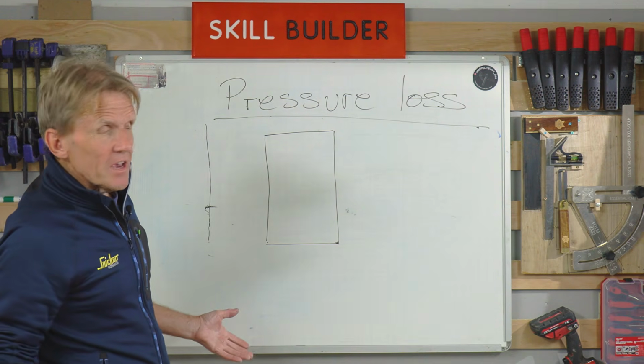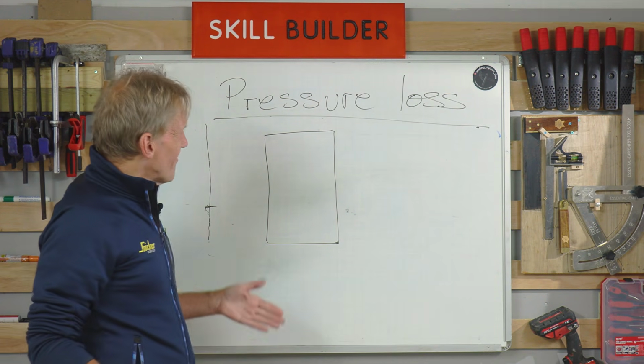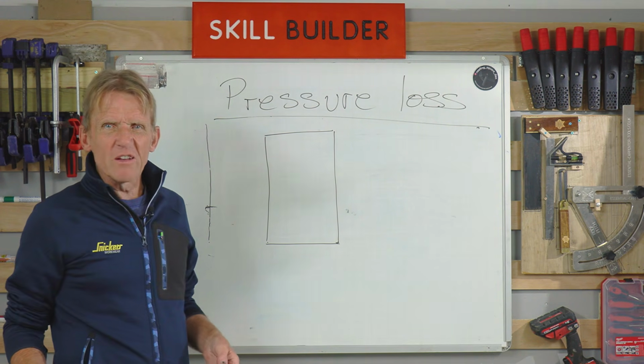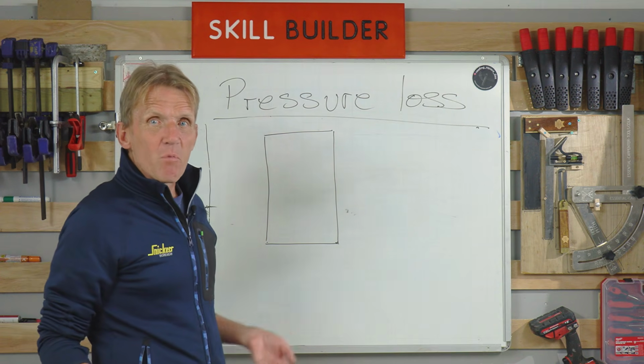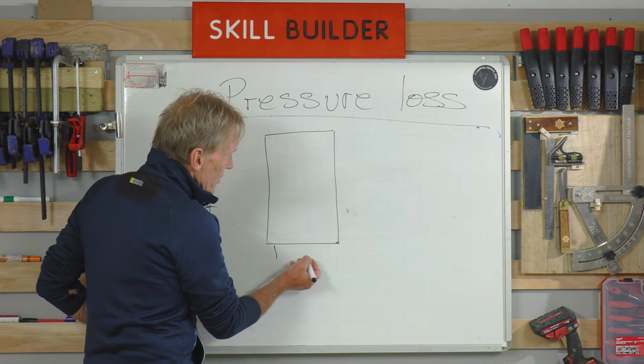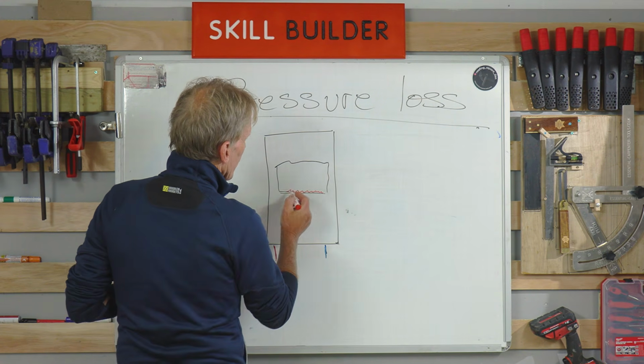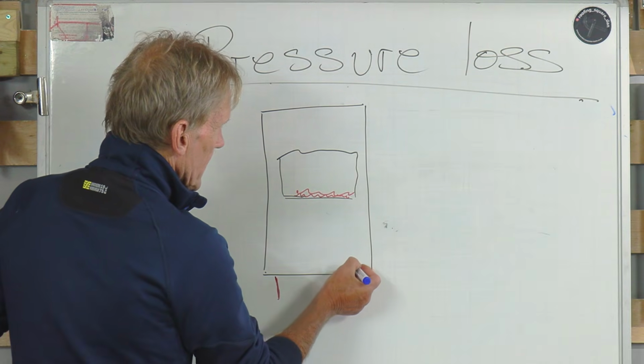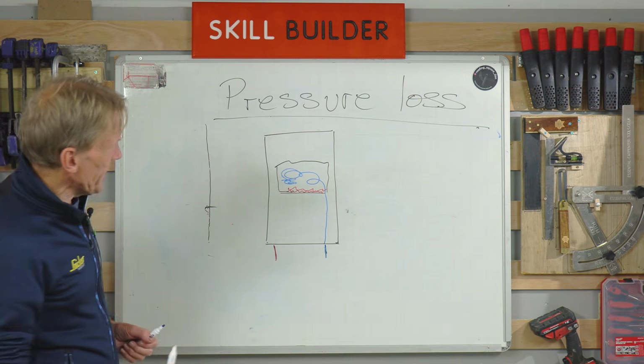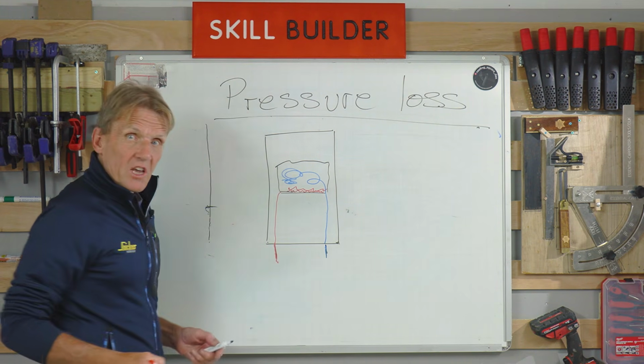Proviso that you've got to be Gas Safe, but we just look at this because there's a lot of engineers who come out and fail to analyse this problem, fail to solve the problem, just have a quick look around and say, oh, you must have a leak somewhere. The only way we can find it, we're going to start hacking up your floors. So they haven't even really done the job of looking inside the boiler. Inside the boiler, we've got our heat exchanger here. We've got our gas there, and the water is coming up into the heat exchanger, going round inside it, being heated up, and coming out hot and going to our system.